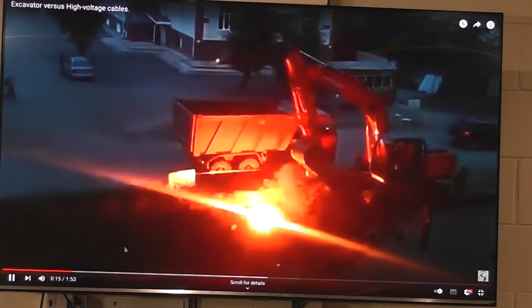So now that's an arc that's been self-sustained by the 11 kV. It'll keep going until the protection system operates. If I see that, you don't see them now, I've run. Watch how these guys respond when it gets hit.